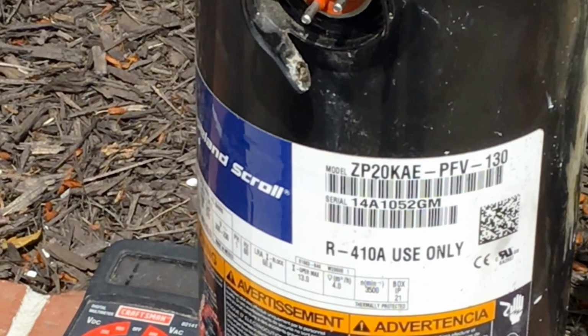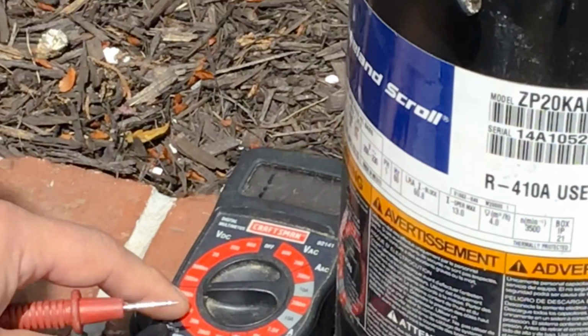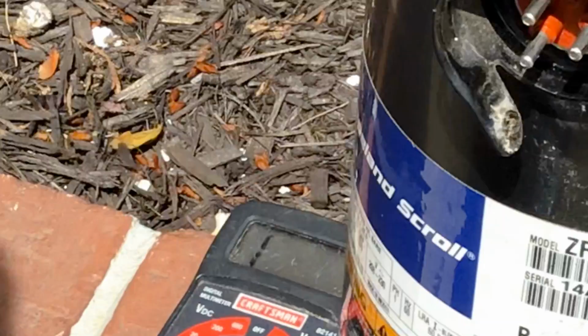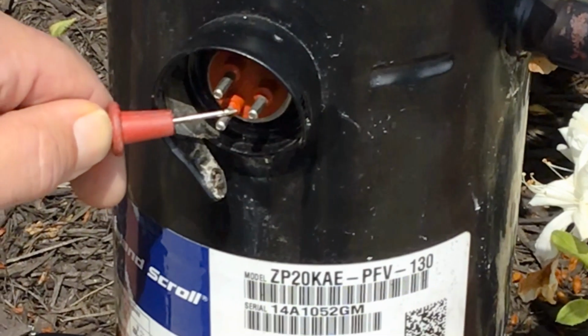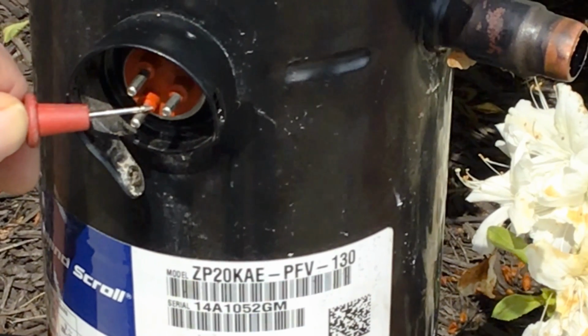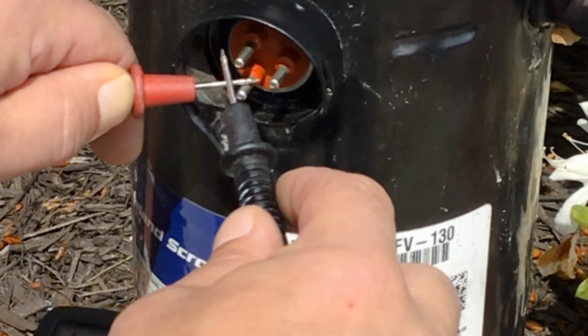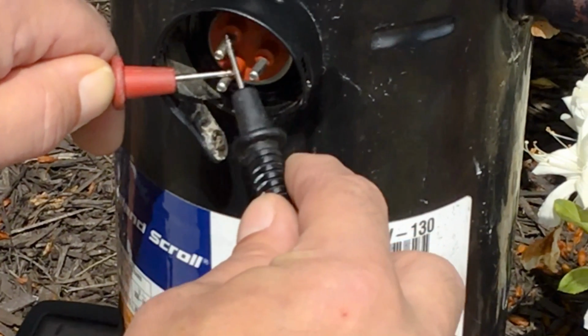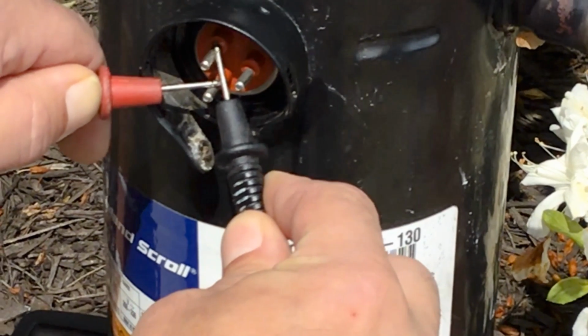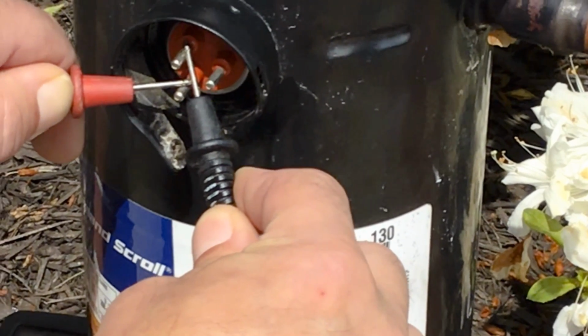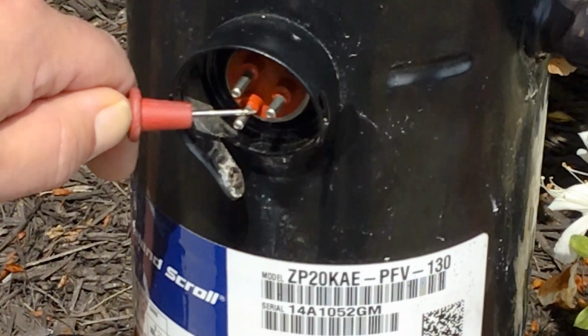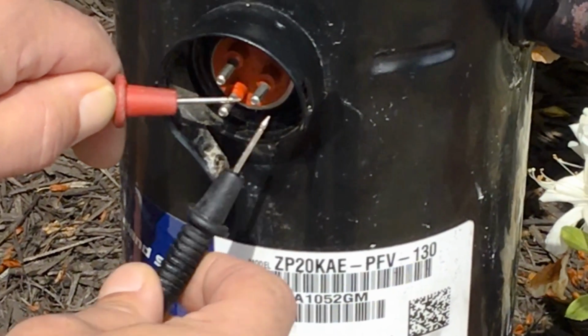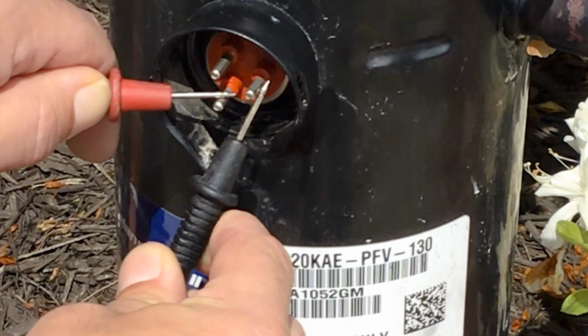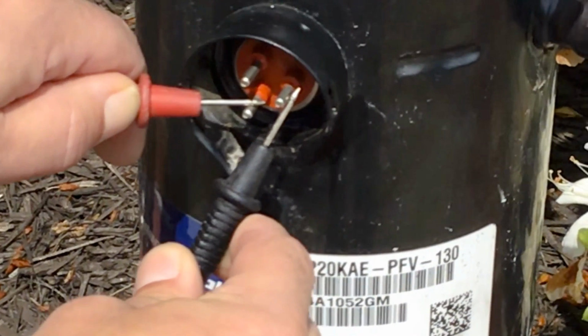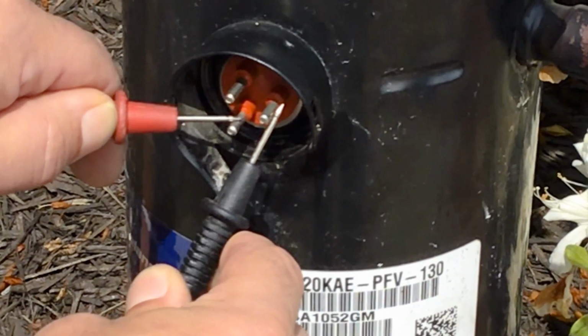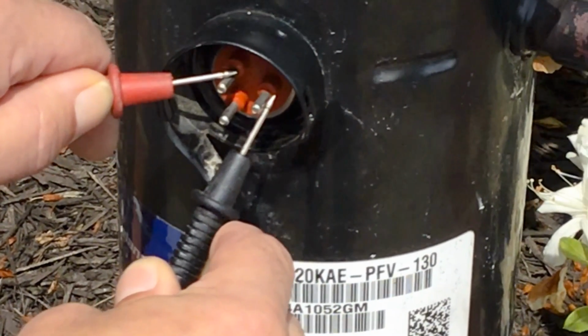So what you want to do is set your meter to ohms at the highest setting, and start at your common pin, your common winding, and then go to your run. That should give you the lowest ohm reading. The next highest ohm reading should be your common to start. And then finally, your highest ohm reading should be run to start.